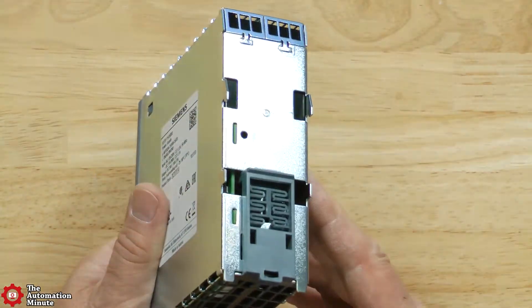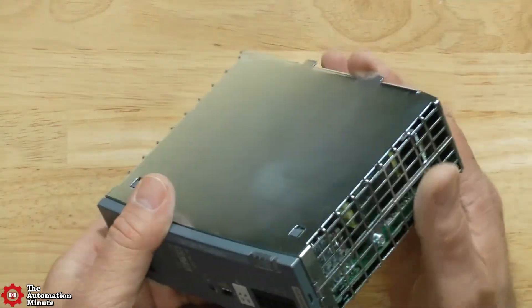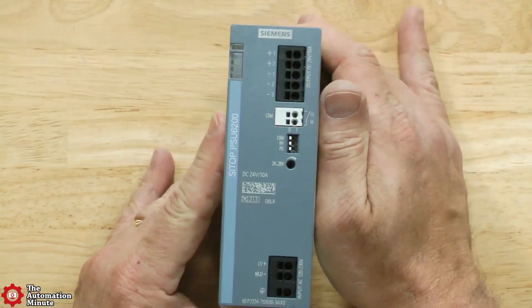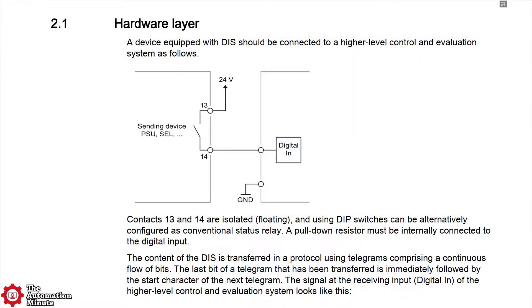The output range is adjustable between 24 and 28 volts DC at 240 watts, and the unit has an overcurrent overload capability of up to 150% of rated output for up to 5 seconds per minute.